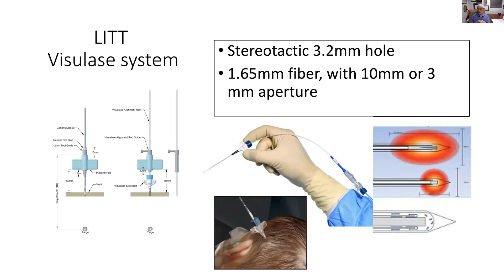And here's an example of a patient of mine having a temporal lobe lesion ablated. You see here the device fixed to the skull just above the child's ear. This is what the device looks like. It's the cooling catheter that's on the outside. It's about 1.5 millimeters in diameter. It has an opening at the end that creates heat by shining the laser light to it. It hits the end of the catheter and then it diffuses into tissue. That heat that's generated is monitored in, quote, real time by MR imaging. In reality, those images are refreshed every 6 seconds, and we measure temperature based on the motion of water molecules on the MRI scan. So this is what was considered the standard of care for children with hypothalamic hamartoma.